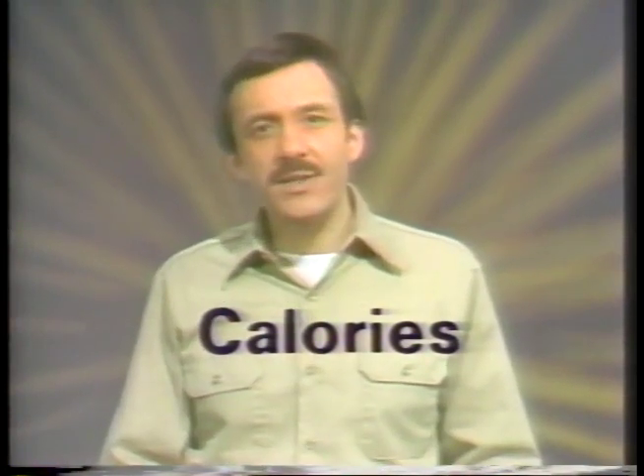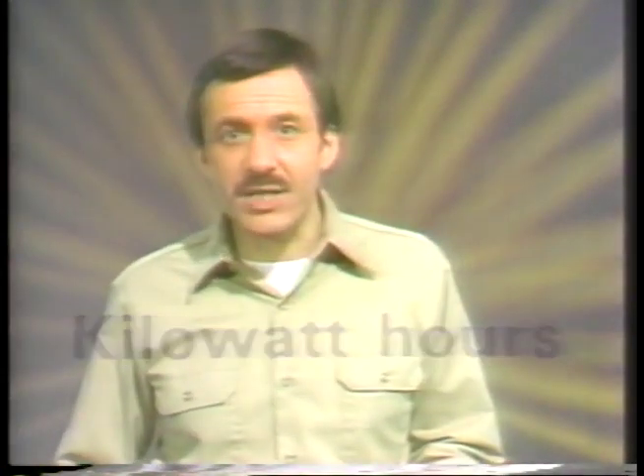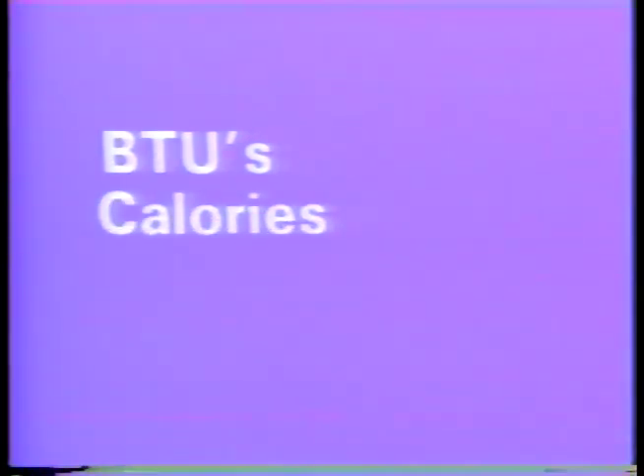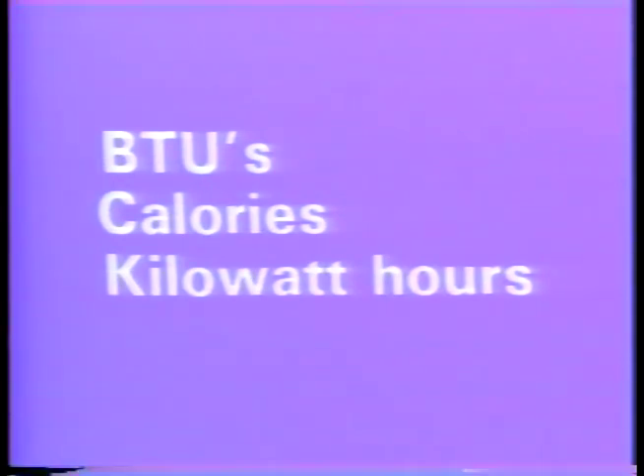BTUs are the units used to measure heat with the Fahrenheit temperature scale. To use the Celsius temperature scale, you must use heat units called calories. A calorie is defined as the amount of heat required to raise the temperature of 1 gram of water by 1 degree Celsius. Both calories and BTUs are ways of expressing heat, just as Fahrenheit and Celsius are two ways of expressing temperature. When heat is produced through the conversion of electrical energy, the energy that's required is usually measured in kilowatt hours. We now have three ways of expressing the energy needed to produce a specific amount of heat. They are BTUs, calories, and kilowatt hours. It may be necessary to convert between these units of energy measurement.